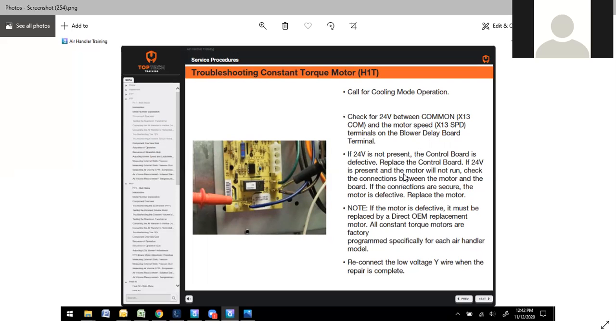If 24 volts is present and the motor will not run, obviously check the connections here. Also check the connections at the motor and the board. And if the connections are secure, the motor is defective. Replace the motor. If the motor is defective, it must be replaced by a direct OEM replacement or an approved OEM replacement for warranty. All constant torque motors are factory programmed specifically for each air handler. And make sure you reconnect your Y wire when the repair is complete.